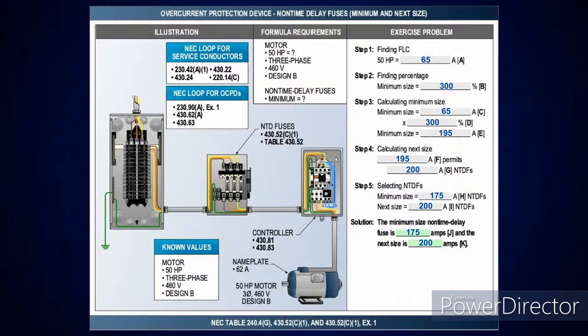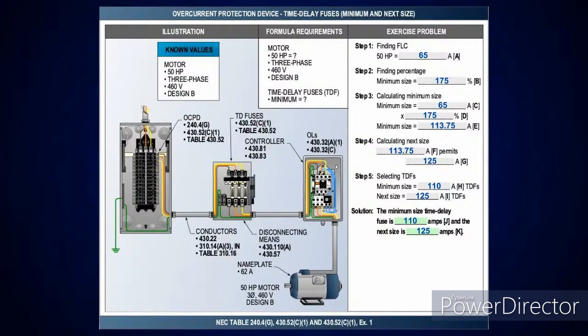That's true, and that's another thing I brought up to them. I said, well, if I pick up 430.52(C)(1) in the 2023 code, and I go down right below that, and you pick up (B), I said, what does (B) deal with? I said, that's maximum. I said, are you telling me I have 2 maximums? And they said, there you go. You're just twisting the code to meet your lies. And I'm like, no, I'm trying to tell you that's what it says. But anyway, besides that, then we'll do the next one, and it's the exact same thing.